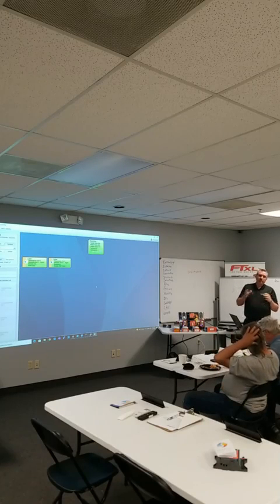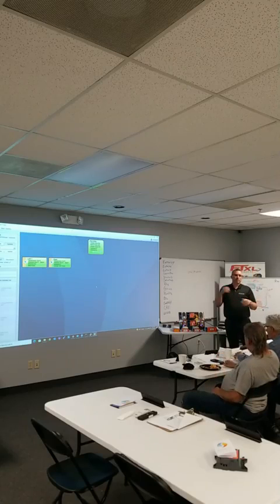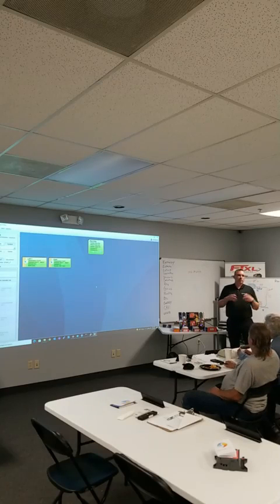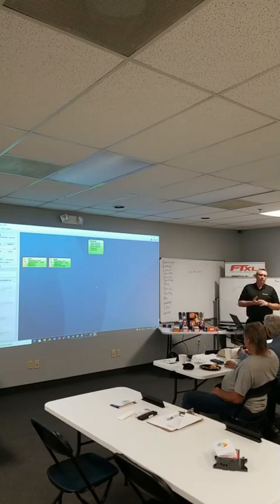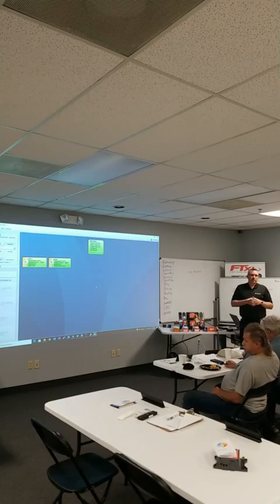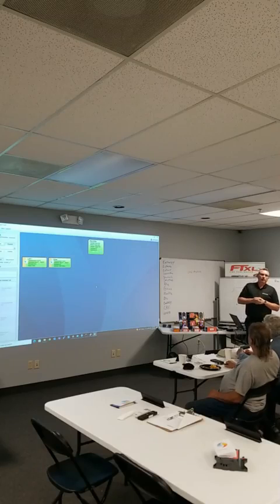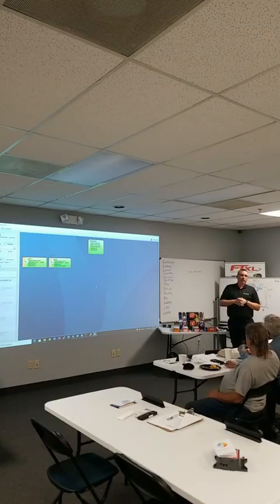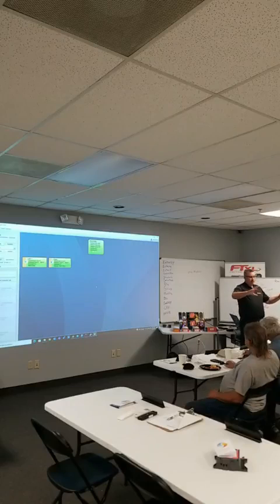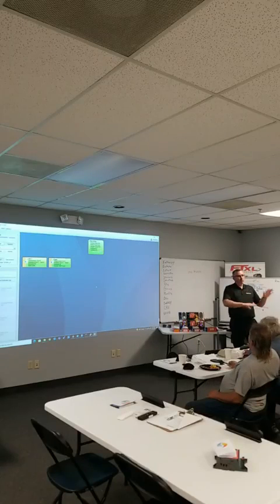So there's a handful of boiler controller, chiller controller, and then we have what's called a Flex IO controller as well. How many valves and pumps could you put on one controller on a hydronic system? Typically, if you're talking about a boiler plant, we just do 2 pumps. If you say you've got 3 or 4 pumps, we can't do a whole bunch of lead lag.